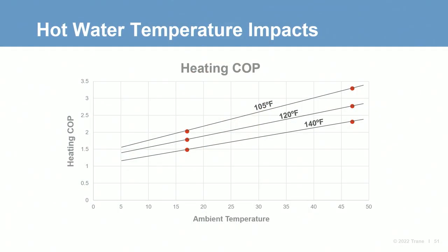Let's analyze that 17 degree ambient point. Moving from 140 degree hot water set point to 120 degree hot water increases unit efficiency by 20%. Moving from 140 to 105 increases unit efficiency by 37%. An easy rule of thumb is that you'll take a 1% efficiency penalty for every increased degree of hot water set point above 105 degrees.